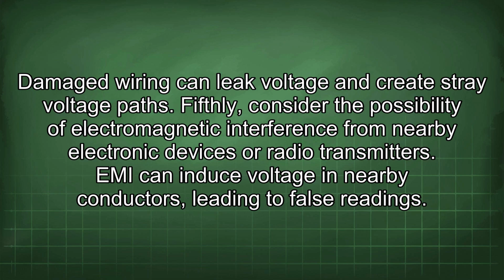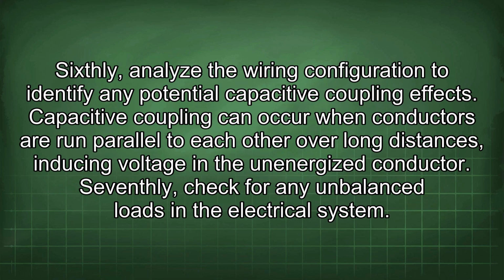Fifthly, consider the possibility of electromagnetic interference from nearby electronic devices or radio transmitters. EMI can induce voltage in nearby conductors, leading to false readings. Sixthly, analyze the wiring configuration to identify any potential capacitive coupling effects. Capacitive coupling can occur when conductors are run parallel to each other over long distances, inducing voltage in the unenergized conductor. Seventhly, check for any unbalanced loads in the electrical system.